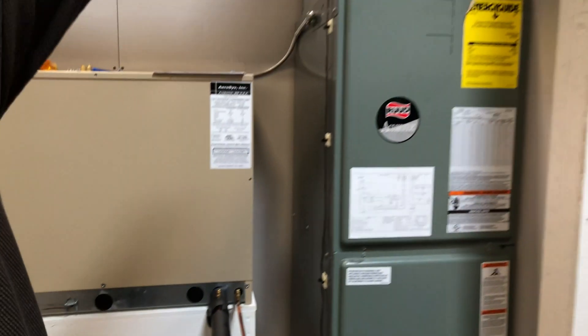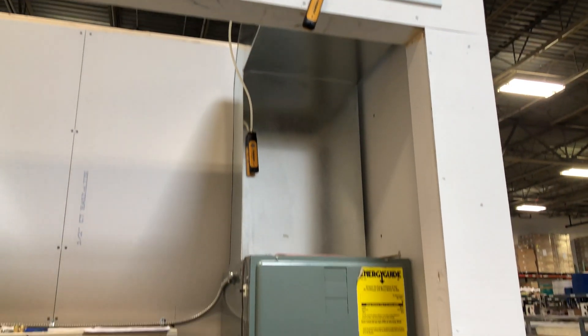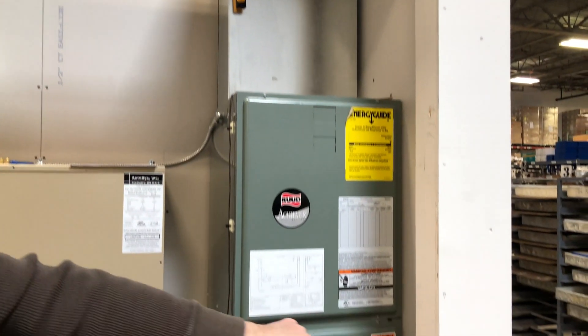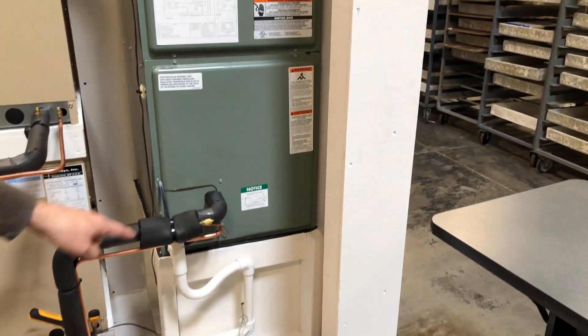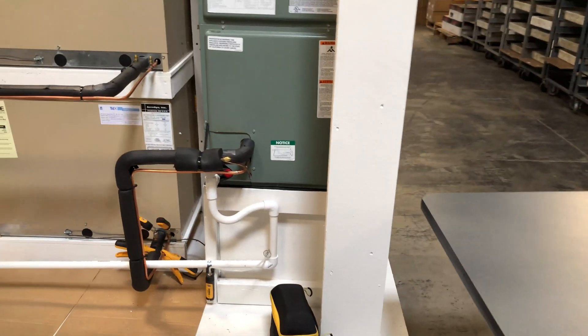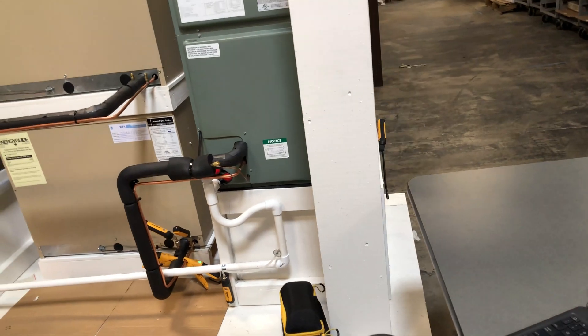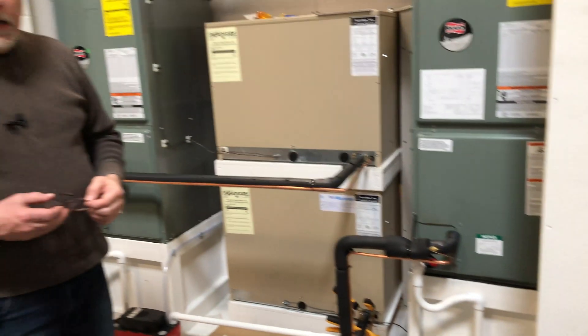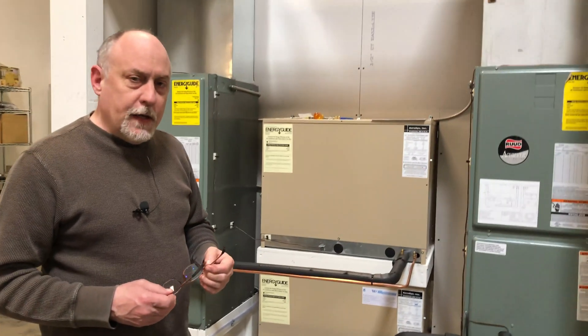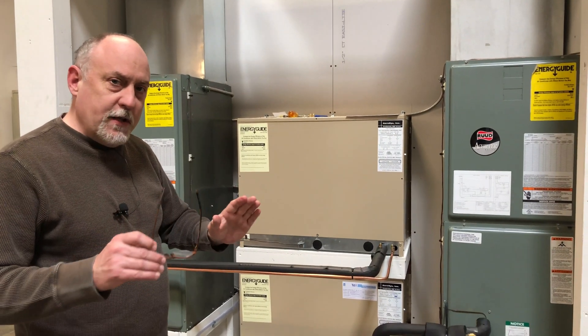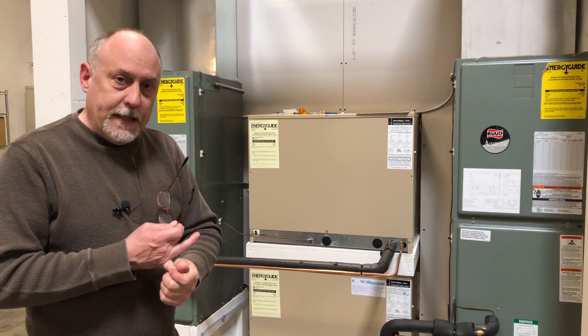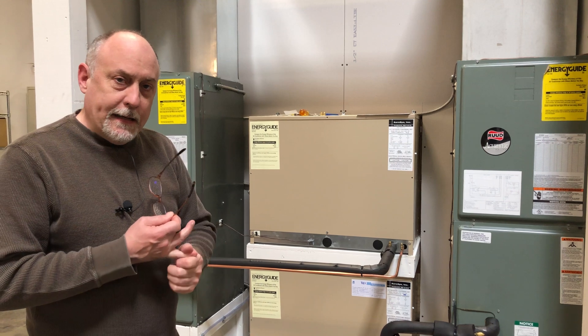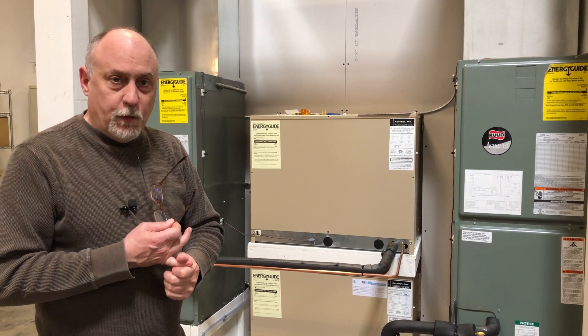I've got a supply air probe up here, a couple of manometers. On the side over there, I've got a return air probe going in the side. And on the front side, I've got an outdoor air probe. All of the pressures on a machine are driven by return air temperature and humidity and outdoor air temperature. Those are the two driving forces.